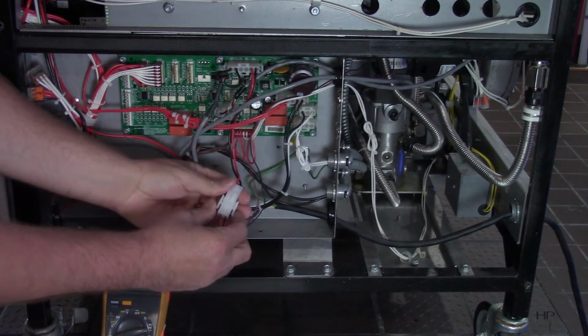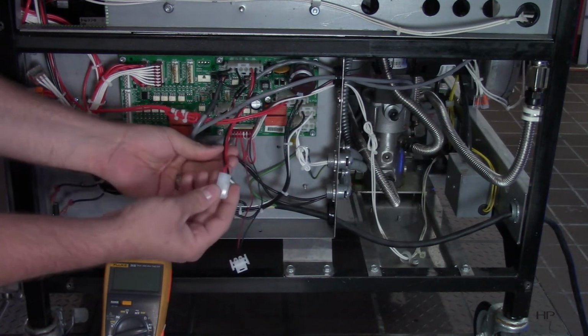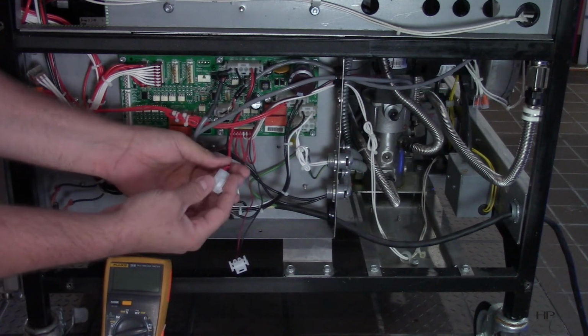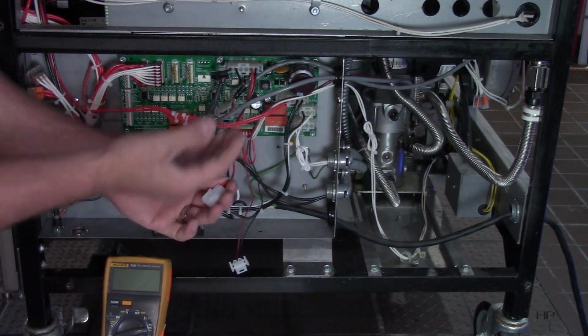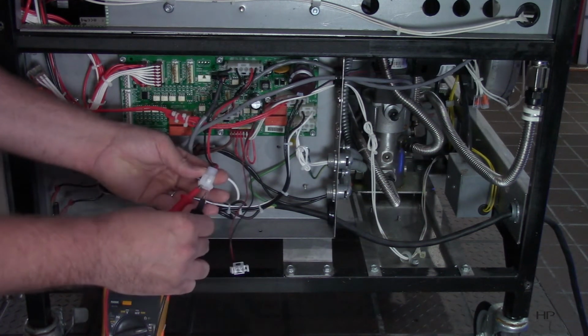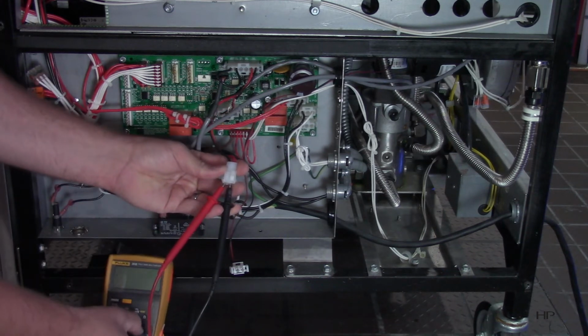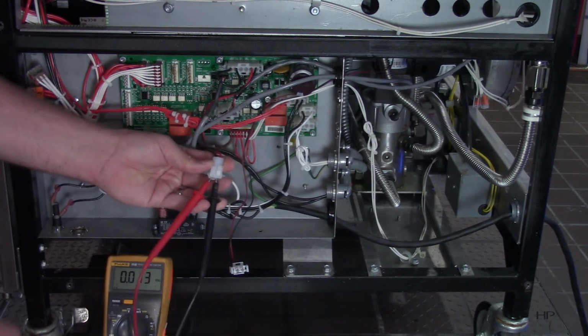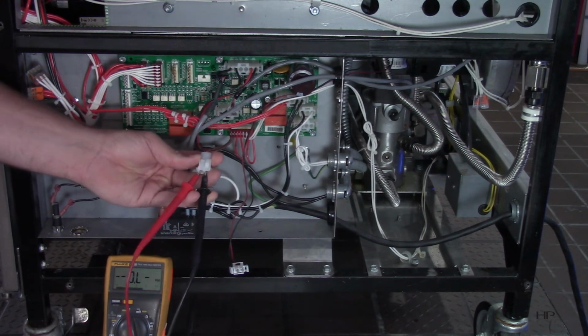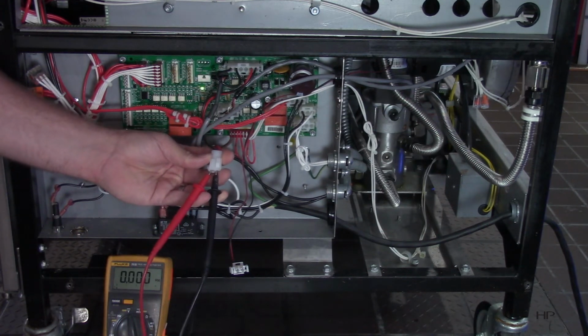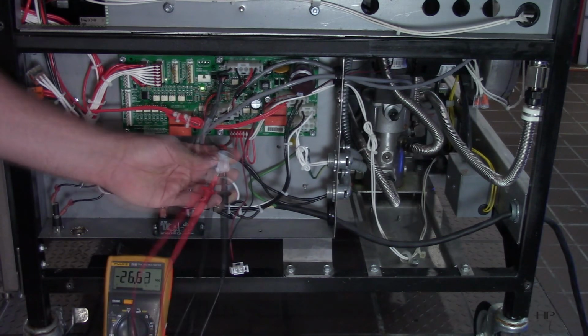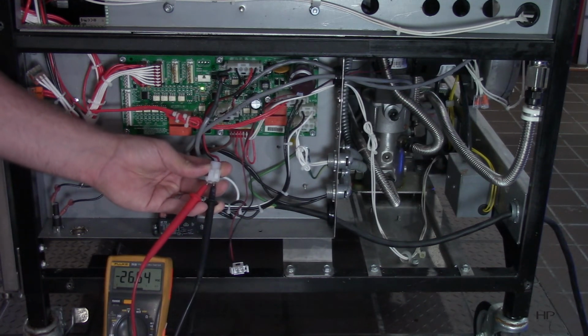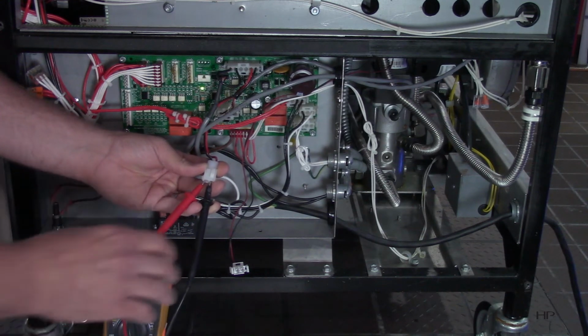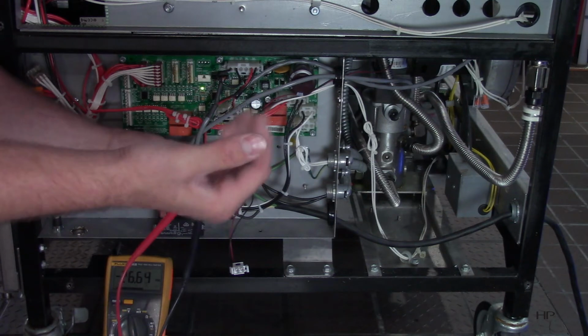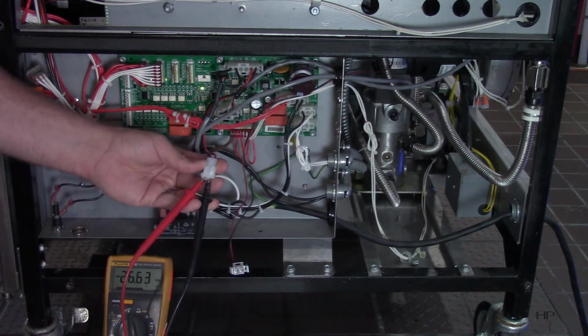We're going to go ahead and unplug this 2-pin connector, which is our supply voltage for our encoder motor. We're looking for 24 volts DC there, coming straight off of our AIF board. Plug in our probes, turn our meter to DC voltage, and then we go ahead and power this unit up. We can be looking for our 24 volts DC. It's not uncommon to see 26 to 27 volts DC. So if we have our voltage here, but we don't hear that encoder motor coming on when it's plugged back in, then we know for a fact that we have a bad encoder motor assembly.